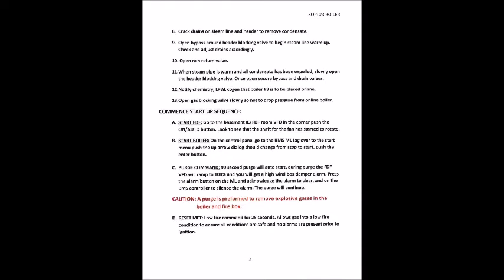B. Start boiler. On the control panel, go to the BMS ML, tab over to the start menu. Push the up arrow; the dialog should change from stop to start. Push the enter button. C. Purge command. A 90-second purge will auto start. During purge, the FDF VFD will ramp to 100% and you will get a high wind box damper alarm. Press the alarm button on the ML and acknowledge the alarm to clear, and on the BMS controller to silence the alarm. The purge will continue. Caution: a purge is performed to remove explosive gases in the boiler and firebox.